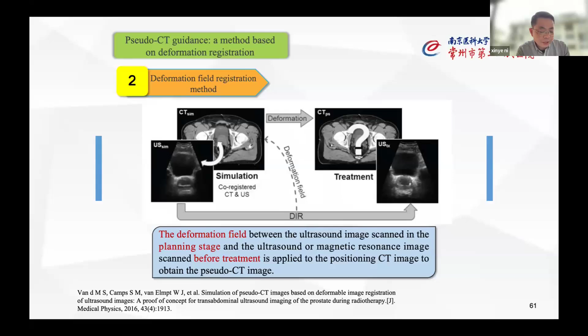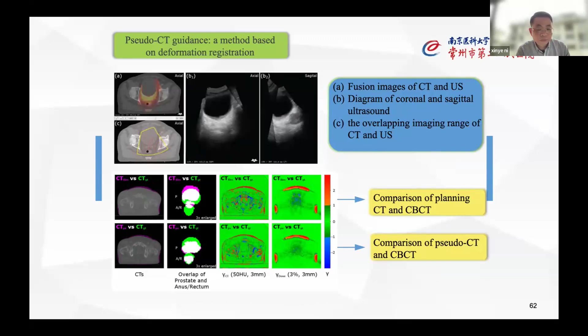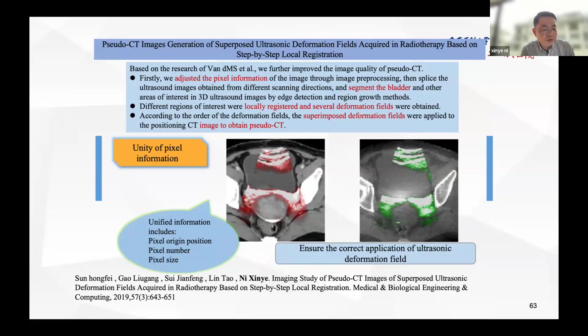This slide showed the fusion images of CT and ultrasound. The organ lines represent the outlines in the ultrasound images, while the red line represents the difference between the two images. We improve the image quality of pseudo CT by adjusting pixel information, splicing ultrasound images and performing local registration of different regions of interest. This method ensures accurate application of the ultrasound deformation field.